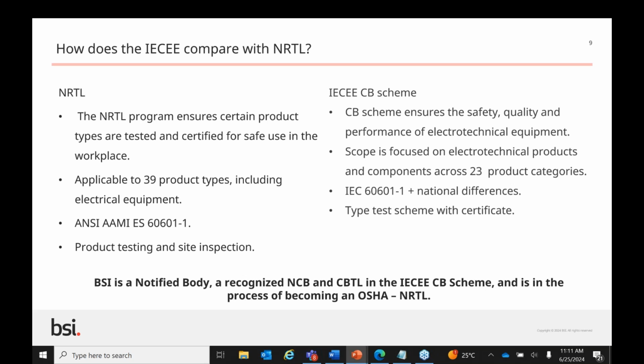The NRTL process comprises two main parts: a factory inspection plus product testing to the standard in that NRTL scope. The NRTL does have ongoing unannounced factory inspections, which are product focused, and they verify procedures are still operating as per the original type test. Whereas the CB scheme is a simple type test with a certificate issued at the end, and there aren't any ongoing requirements. So I'm pleased to announce that BSI have lodged an application with OSHA to become an NRTL for medical devices, which means BSI would be able to support with NRTL, the IEC CB scheme, and notified body approvals like MDR and MDSAP. Next slide, please.